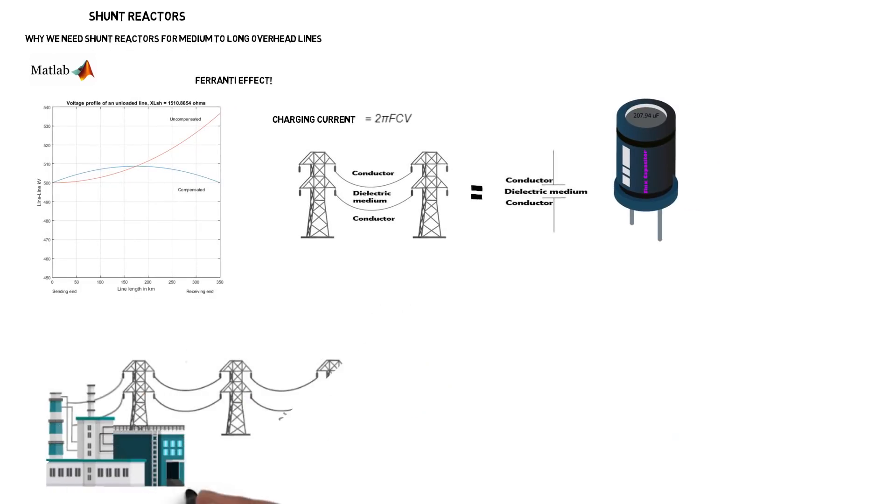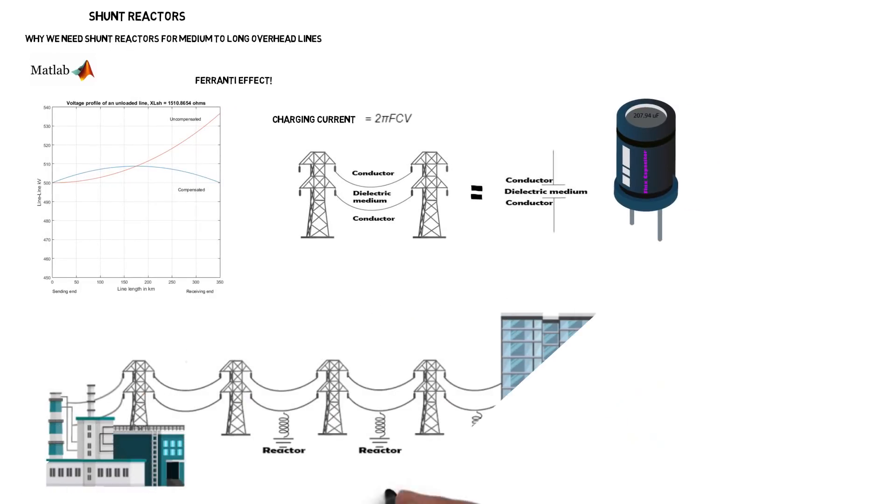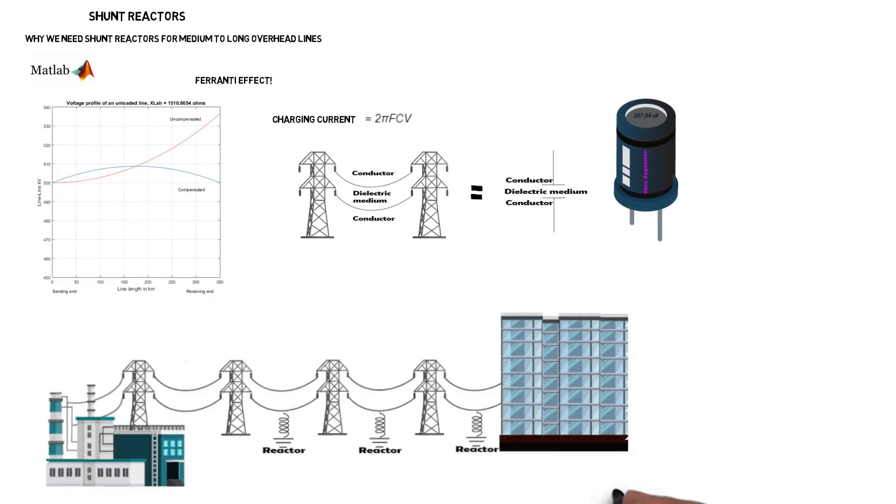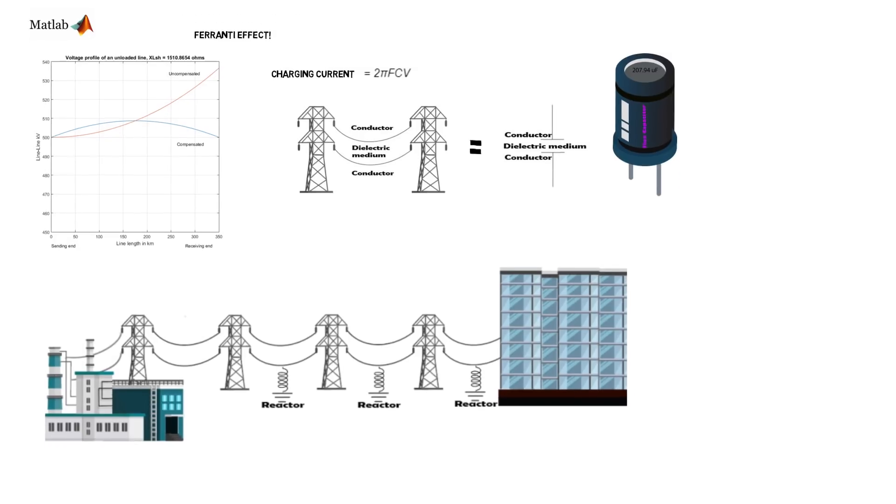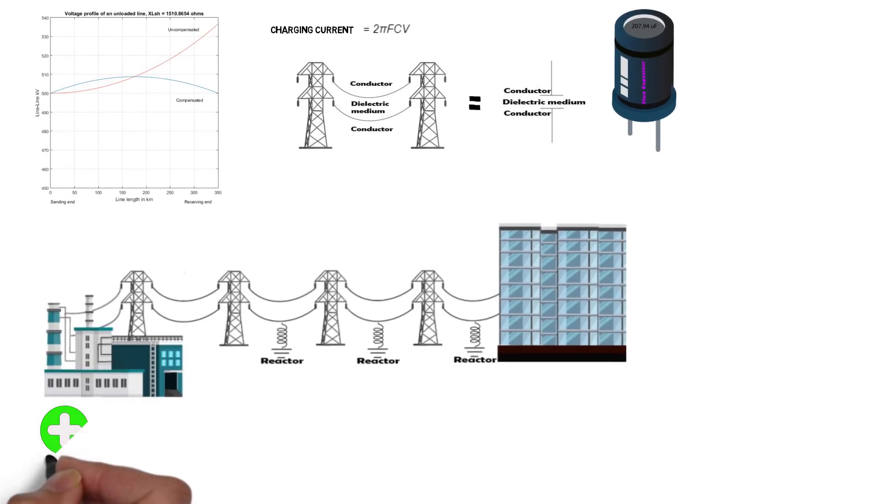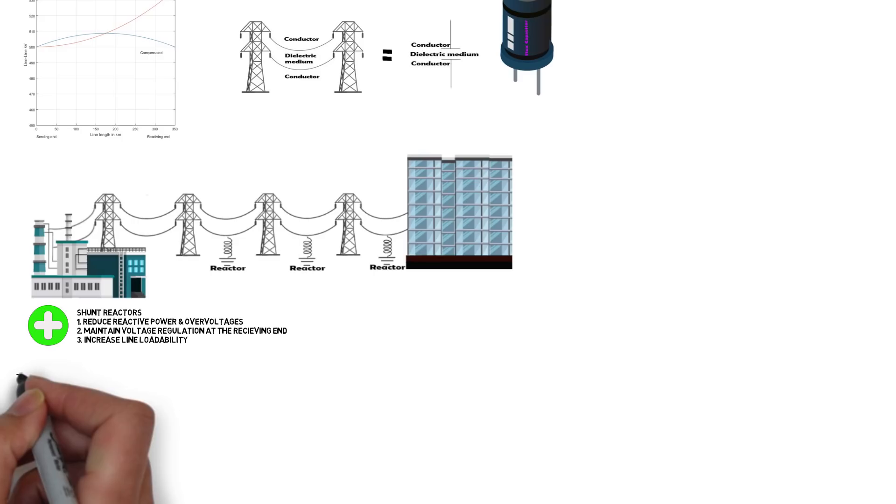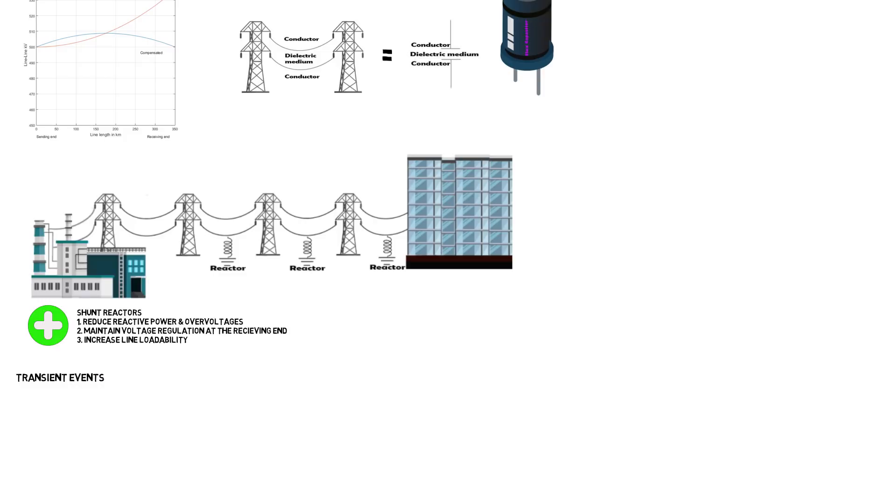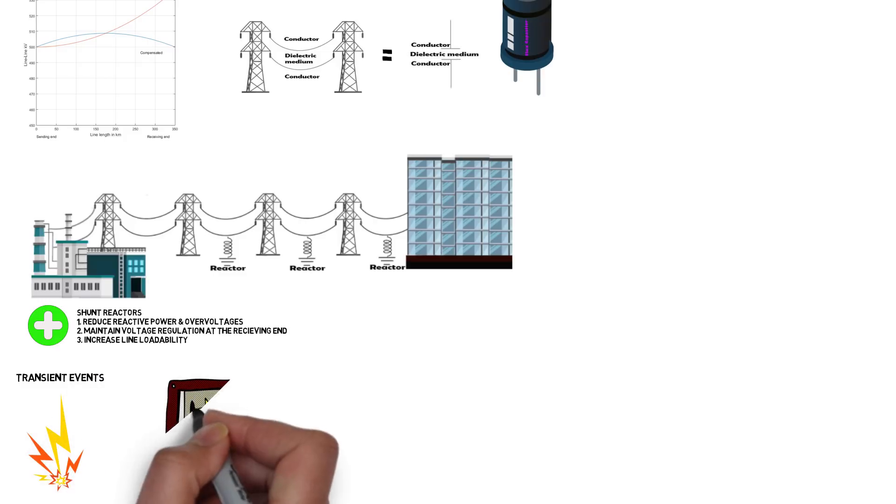Shunt inductors are usually installed at the receiving end or at points along the line from phase to neutral for all phases. Reactors by definition can absorb unwanted reactive power, reduce over voltages and maintain the voltage at the receiving end. For transient events such as lightning and switching, reactors will reduce any over voltages.